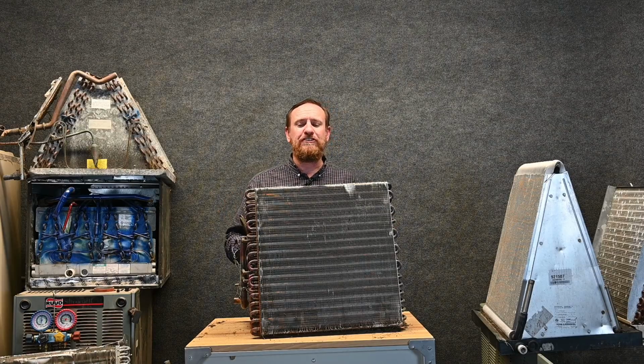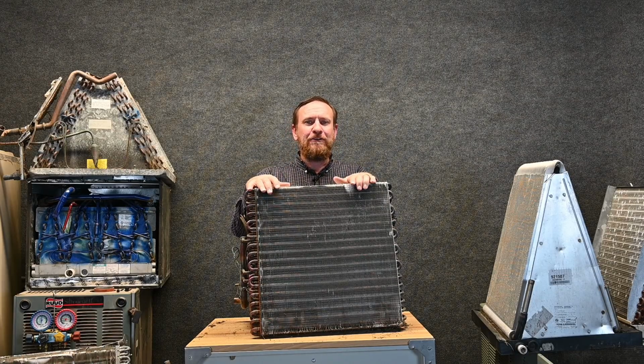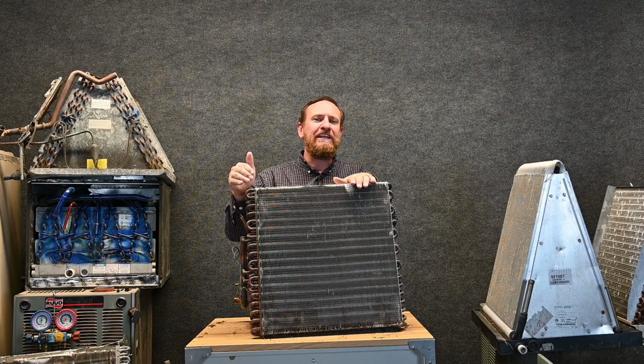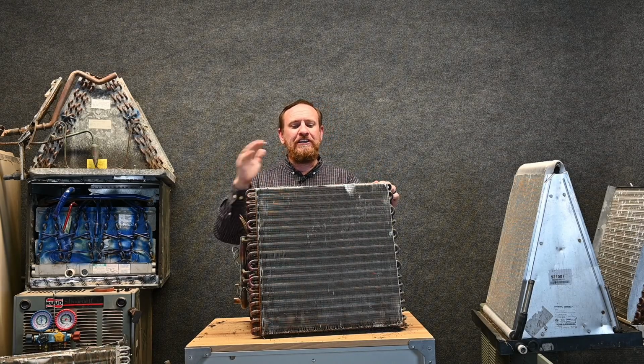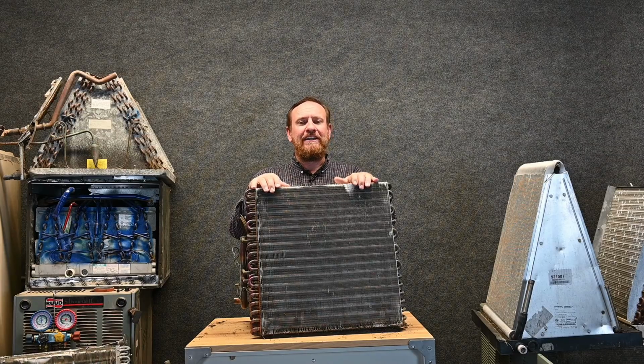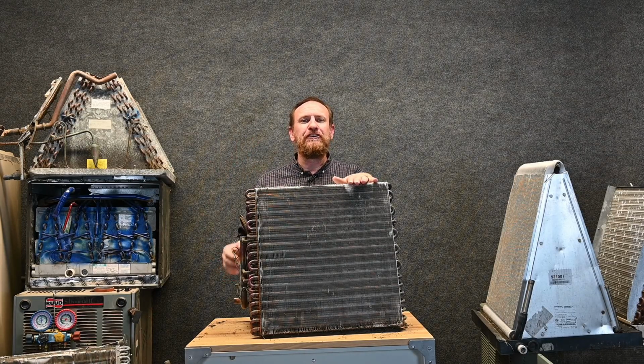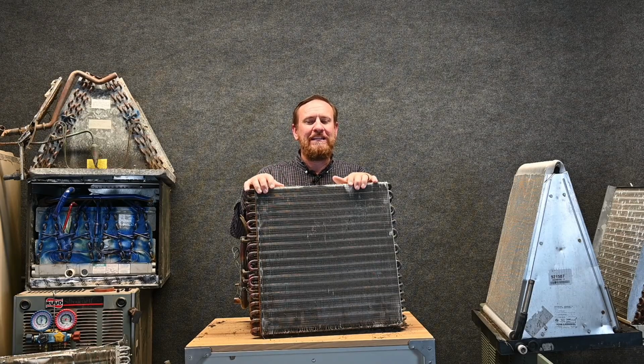So you have two different issues going on. If we pull a proper vacuum, we should never have an issue with refrigerant leaking from the inside out, which is a big issue with the evaporator coils leaking. On the other side, the chemical side, it's important that we use as few chemicals as possible, and we use a good filter to help collect as much of the particulate as we can.